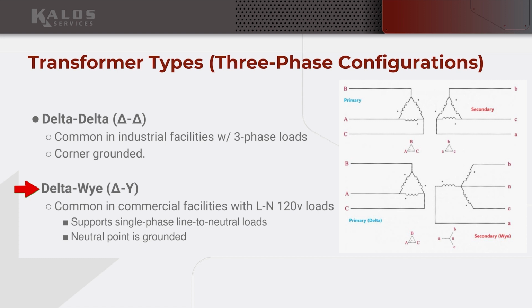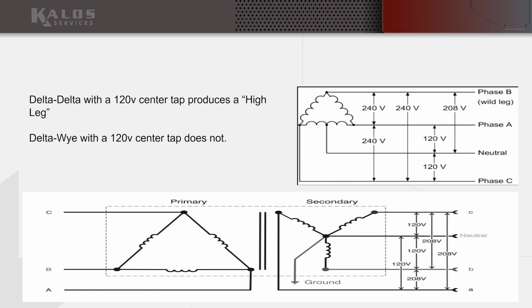And so we can see the difference here between delta being wired in a triangular pattern. Y is wired in what you might call a star pattern, right? To where only one side of each winding is connected in the middle. And then in this next slide, I show where we would pull a neutral off of that middle point. So we're going to get more into the actual wiring of these transformers in one of the future classes.